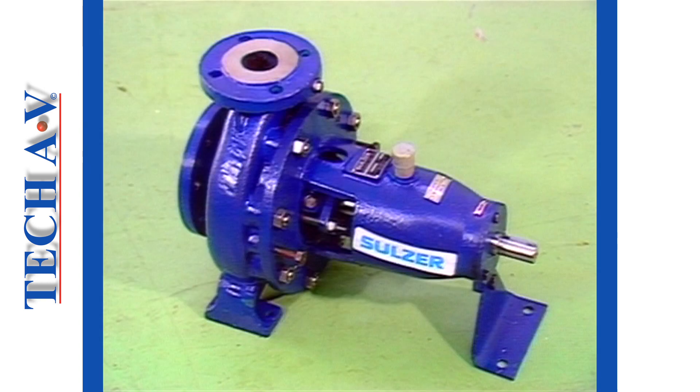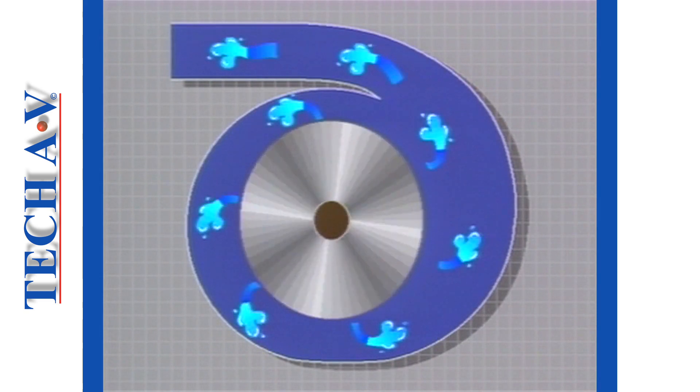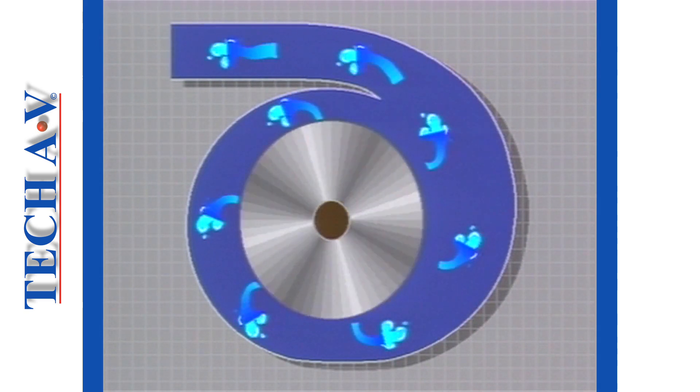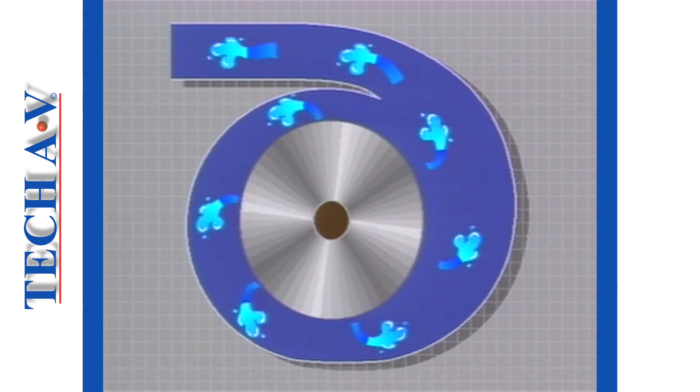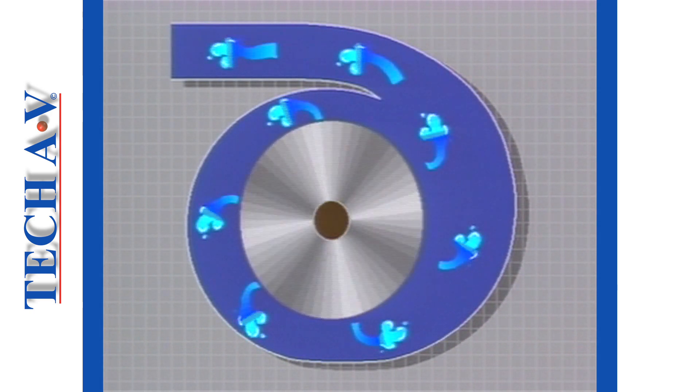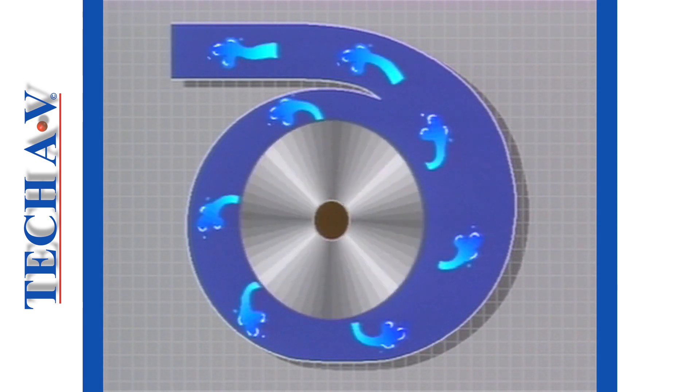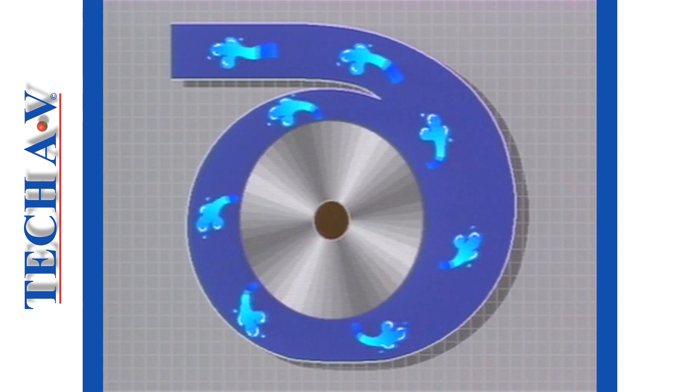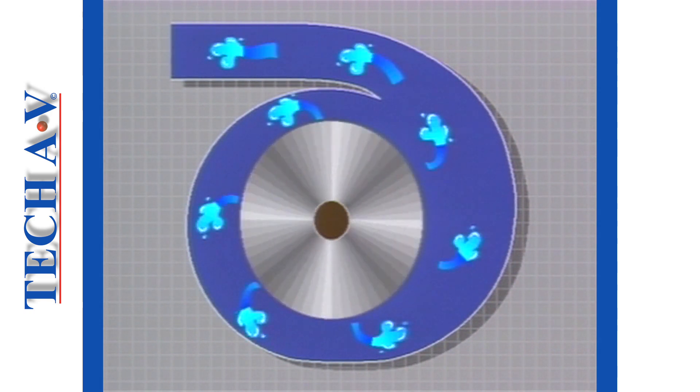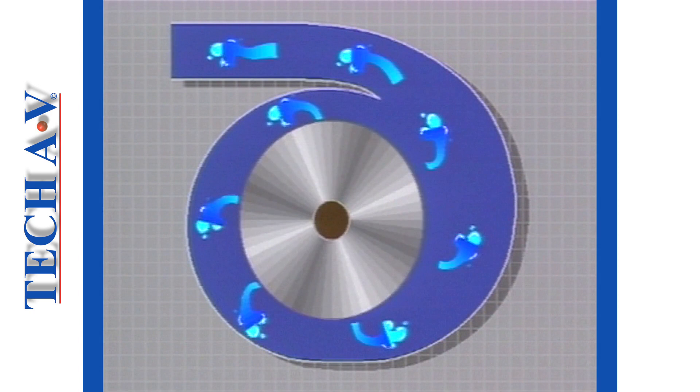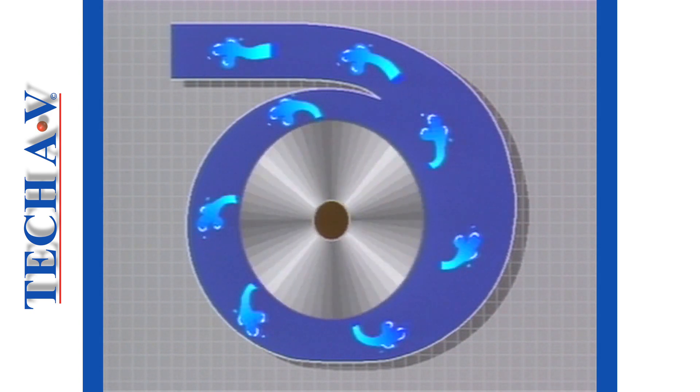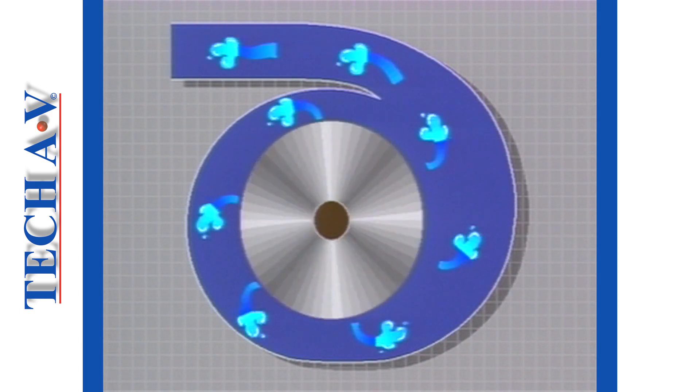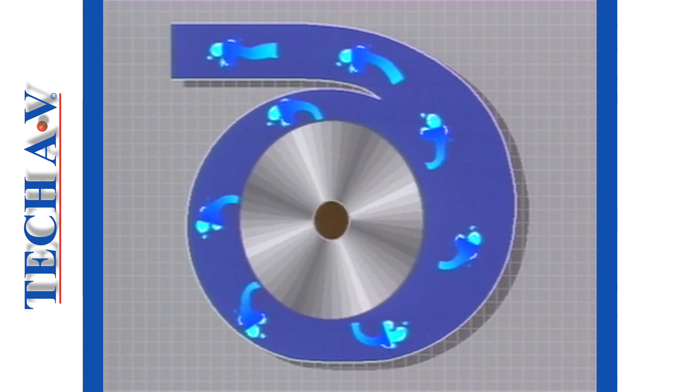Let's overview the operating principles of a pump such as we have just discussed. The impeller rotates within the casing, which is filled with water or liquid. The impeller's vanes throw the water outward under centrifugal force. The amount of energy imparted depends on the speed and physical size or design of the impeller. The energized water is now forced into the cavity surrounding the impeller and thereafter discharged through the discharge or delivery outlet.